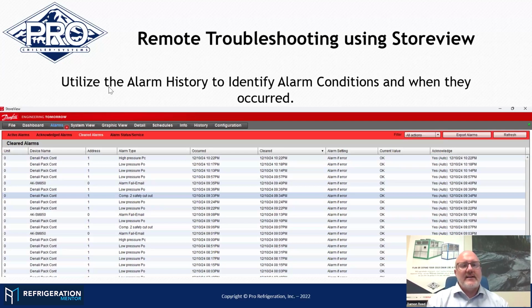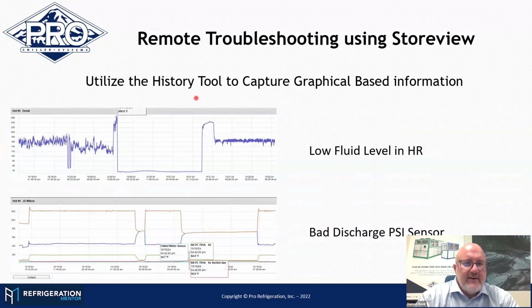That's how I always like to look at it: what happened before, what happened during, and then what happened after. And I don't get too deep into it. My first pass is going to be pretty fast: what happened 4 or 5 minutes before, 4 or 5 minutes during, and 4 or 5 minutes after. And then if I have questions or if I can't piece the puzzle together from that, then I'll go in and utilize the history tab, and I'll show that later in a slide right here. So the history tool gives you the ability to graph and take a look at, okay, historically what had happened on a system.